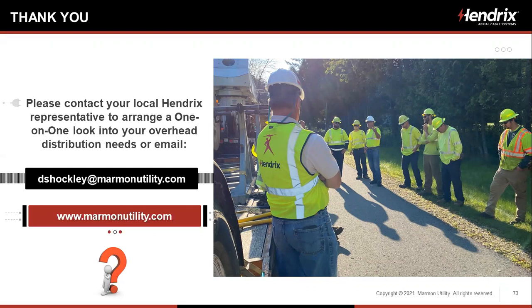Now, that's not to say that if I had a static forest fire, okay, so the forest is on fire, there's very little wind, it's not moving, and there's a lot of fuel. If I've got 1900 degrees Fahrenheit at a height of 25 feet in the air, yeah, that high density polyethylene is going to melt and come down, but probably everything else is down already. So how do we fare in forest fires? Pretty darn good, as long as it's moving. If it's static, nothing's going to survive.